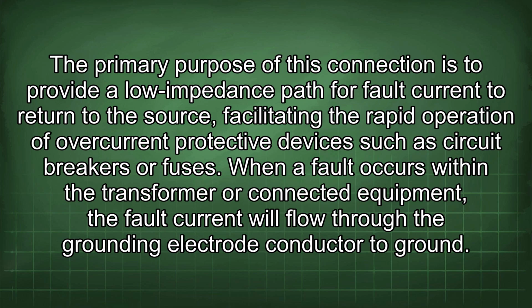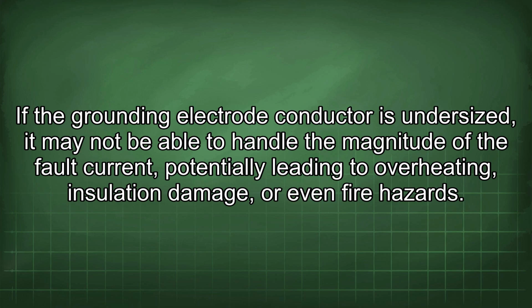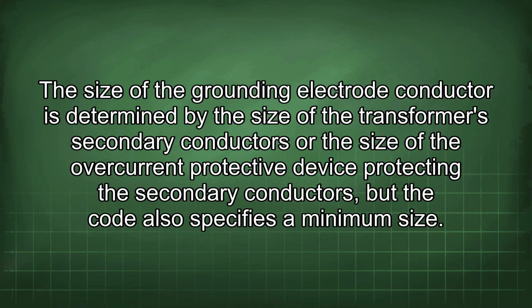When a fault occurs within the transformer or connected equipment, the fault current will flow through the grounding electrode conductor to ground. If the grounding electrode conductor is undersized, it may not be able to handle the magnitude of the fault current, potentially leading to overheating, insulation damage, or even fire hazards. The size of the grounding electrode conductor is determined by the size of the transformer's secondary conductors or the size of the overcurrent protective device protecting the secondary conductors, but the code also specifies a minimum size.